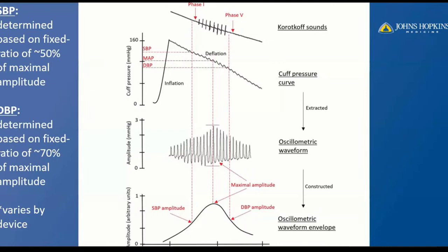In contrast, automated devices use a similar cuff inflation to the point at which the brachial artery is constricted. But at some point during inflation or deflation, the cuff senses variations in volume and vibration, leading the device to develop a cuff pressure curve, which is extracted into an oscillometric waveform and then constructed into an oscillometric waveform envelope. This envelope allows us to visualize and calculate the maximal amplitude, an estimate of the mean arterial pressure. Using fixed ratio coefficients and algorithms, the envelope allows the device to provide the output of systolic and diastolic blood pressure.